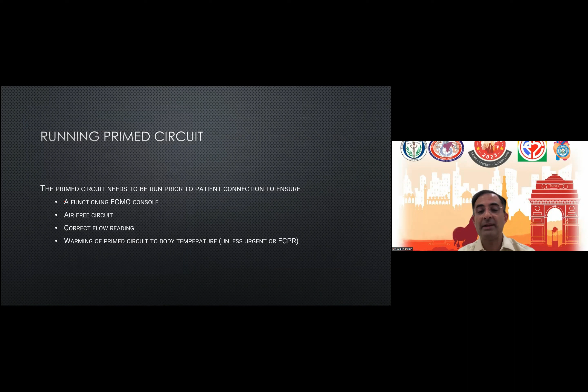Certain other things that we do is to make sure that the flows are recorded. This is done by ensuring adequate ultrasonic paste on the flow sensor on the pump head. If the flow is not indicated, or you get 3 dashes, or the flow is showing a 0 in spite of the pump functioning, disconnect the pump, reapply the ultrasonic gel, and again reattempt running the ECMO on the console with the prime fluid.